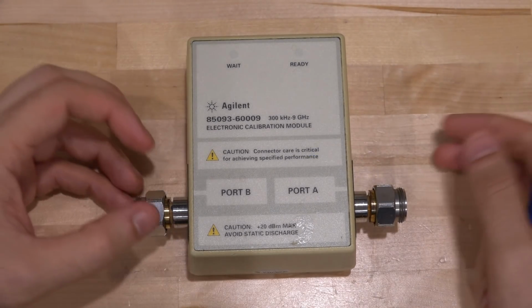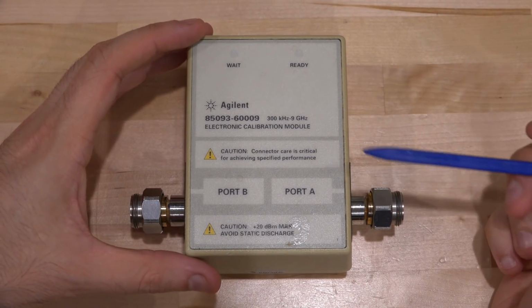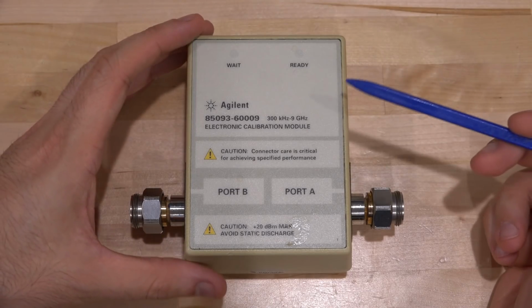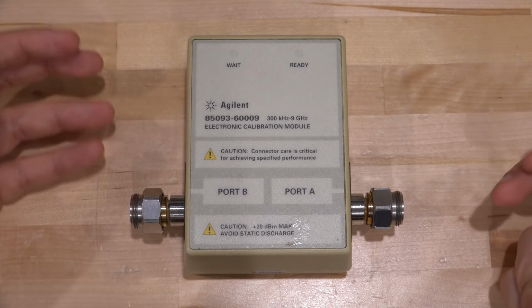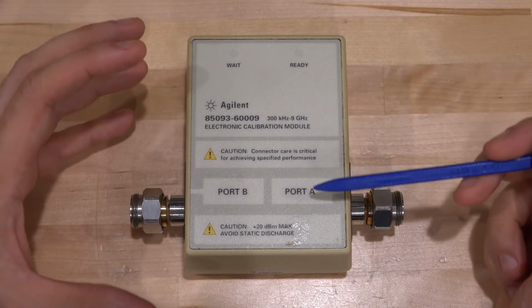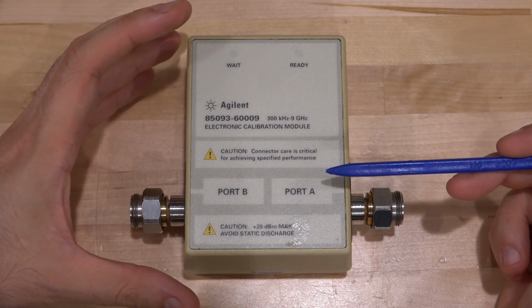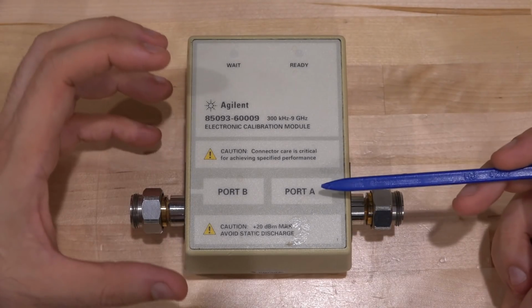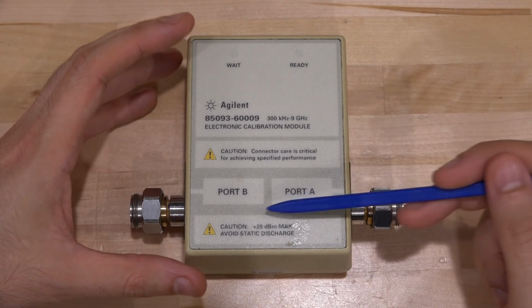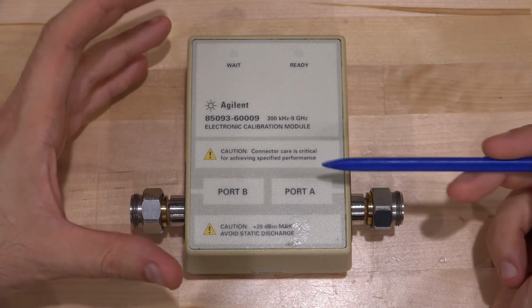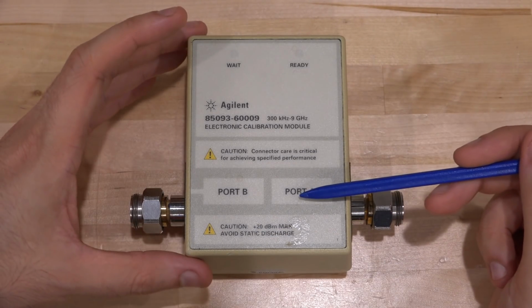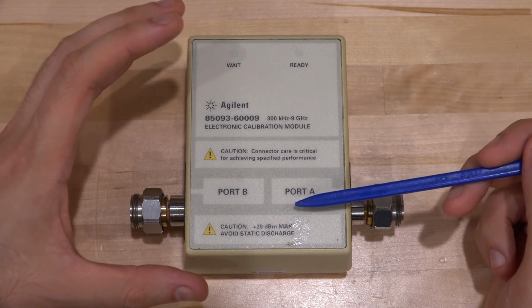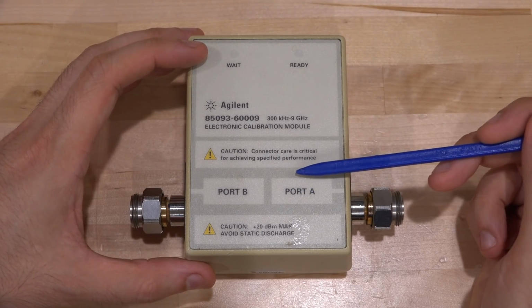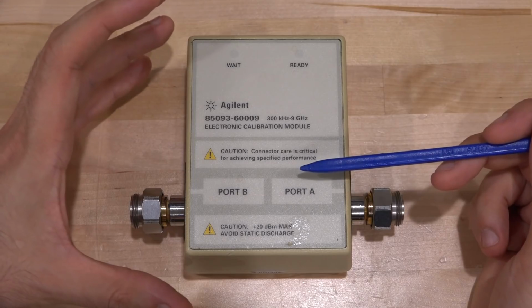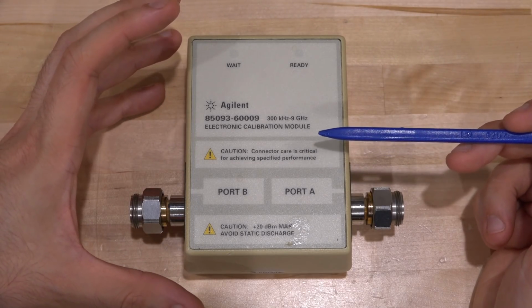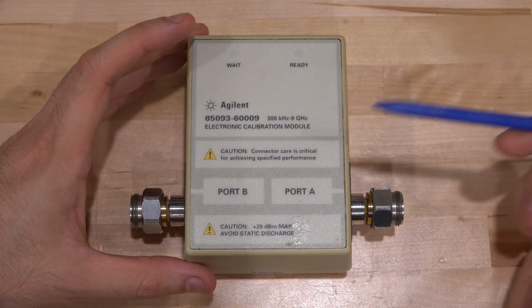The ECal module only has one port connection, but it also has some disadvantages. First of all, it's quite a bit more expensive than a coaxial calibration kit like the one you saw. And at the same time, it has some power limitation because it has some switching inside done in solid state, typically done with pin diodes in order to switch the different standards. And that makes this have some maximum power limitation too. In this case, this is 20 dBm for damage, but slowly it's going to become not as good in terms of its calibration functions. At the same time, you can store the exact response of this on an EEPROM inside of it. So it will download that into the network analyzer, and then there's no doubt what the calibration standard specifications are. It's perfect, especially when these things vary with respect to each other.